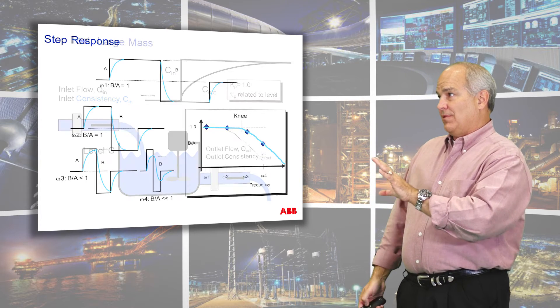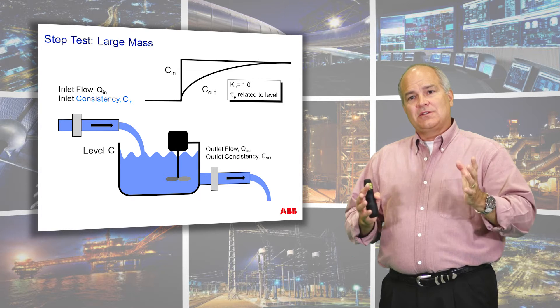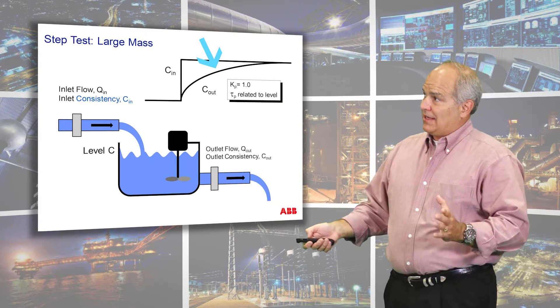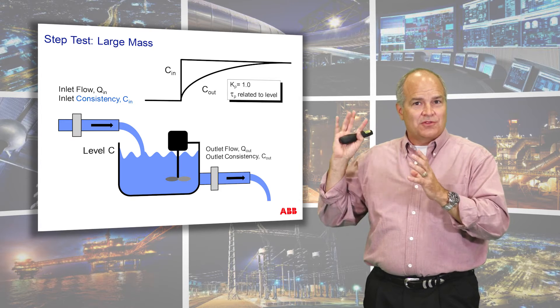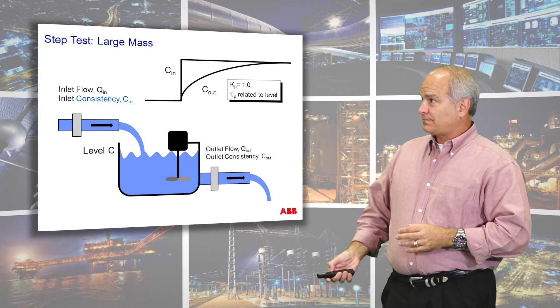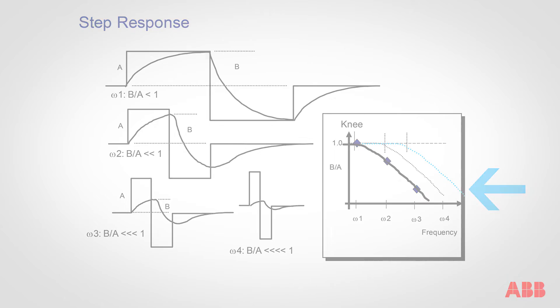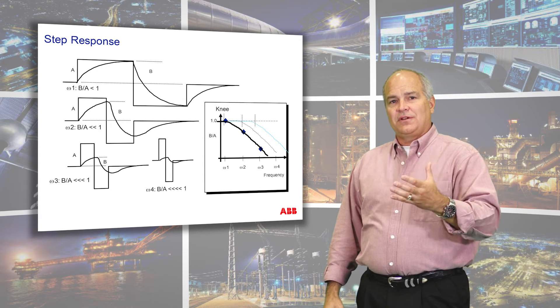To further exemplify this: if you have a high tank level, you have a lot of mass, a lot of mixing, a lot of energy. When I change that consistency, it's going to take longer because that whole mass has to hit equilibrium before our process reaches the output. This would be equivalent to tuning a loop very, very slow. So when I talk about closed loop time constants and mass, I'm thinking of a tank and its volume. Here I've just barely got the frequency aligned with how long it takes — right at an amplitude ratio of one. Then I go faster and faster, and because of the mass, the frequencies are being absorbed much faster. So this is what we're getting into: Bode plots and the frequency content of our process.